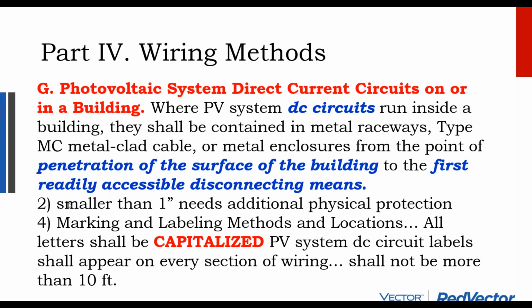That said, DC circuits, they're required to have this extra physical protection of metal, and they have to be marked and labeled. Every 10 feet, you need a sticker that says this is a solar circuit. Every 10 feet inside that building and outside that building, it needs to be marked.